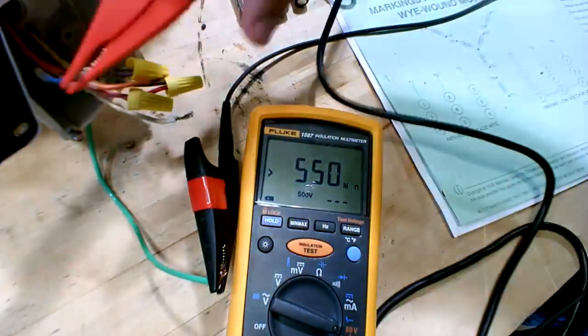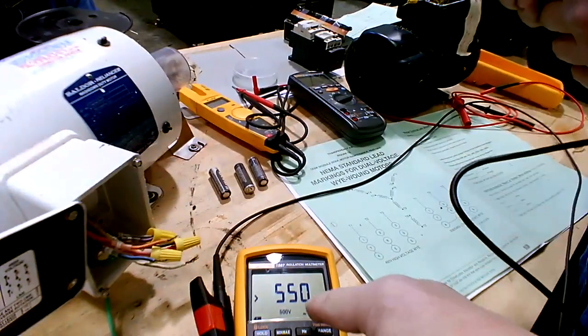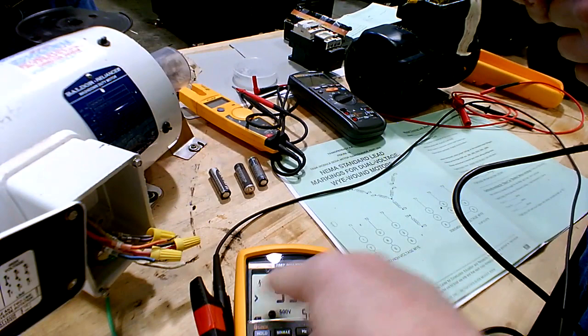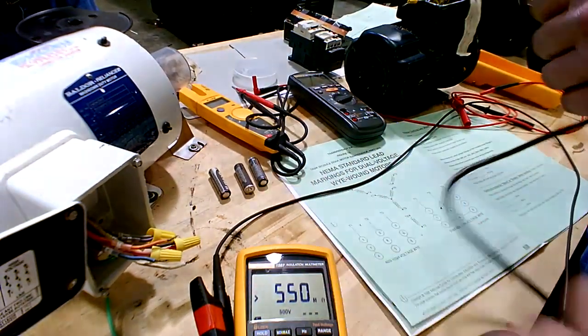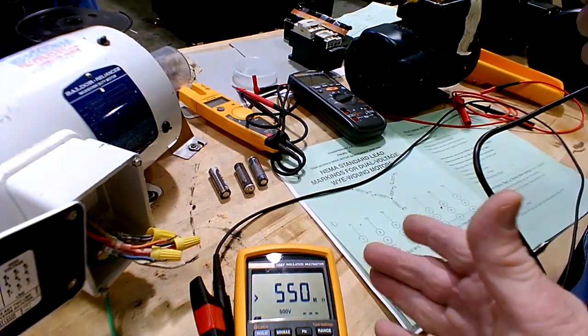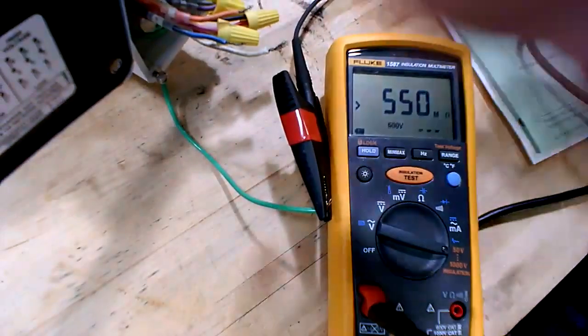Now watch, you take it loose and have it in the air like that, touching nothing. Hold the button with an open circuit and watch it. Greater than 550 megohm. That's like an open circuit because it can't read higher than that. It can't read higher than 550 megohm. So that leg is okay. Go to the second leg.